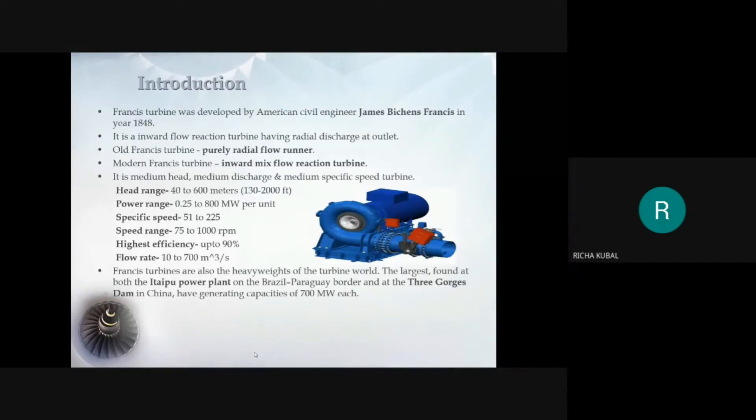The turbine which is mostly used today is modern Francis turbine which is known as inward mixed flow turbine, which means water enters towards the center in radial direction and discharges out of runner axially. The turbine is a mixing of impulse and reaction turbine, the only difference in its amazing design of blades. The blades rotate using both reaction and impulse force of water flowing through them. The ability to use both the kinetic and potential energy to produce power hence is known as mixed flow turbine and is the best modern turbine widely used in hydropower plants.